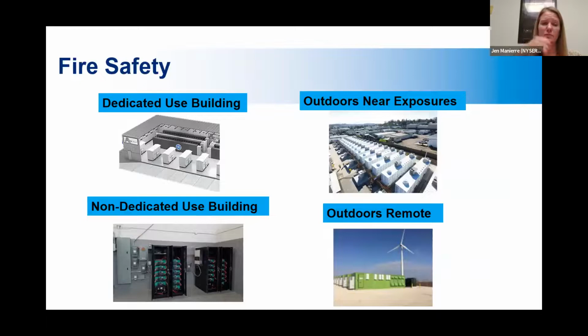I alluded to this before, but throughout the fire code, the requirements for the systems differ based on not just the technology type, like we've seen in some of the charts so far, but also where they're located. A dedicated use building is designed to do nothing but hold batteries for the most part. It's going to have fewer restrictions than a non-dedicated use building that also has human occupants inside. The non-dedicated use building is going to have the most stringent requirements of all.